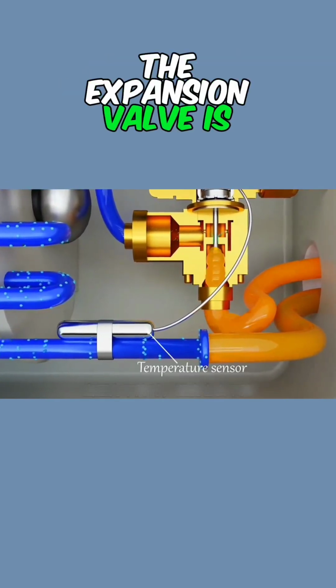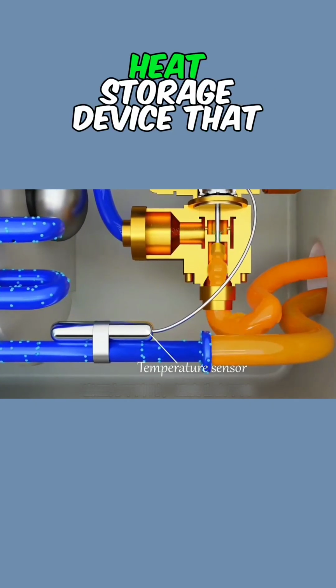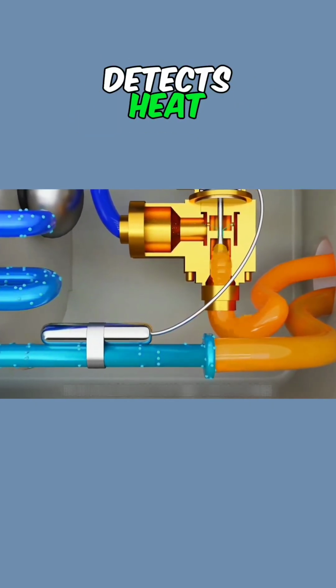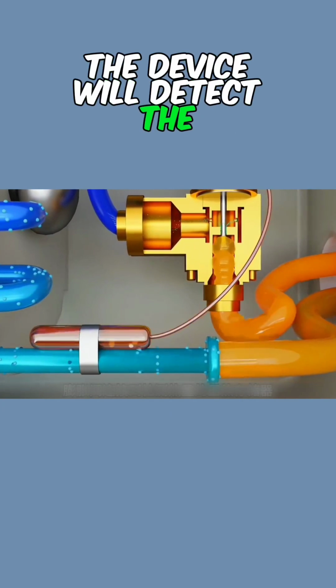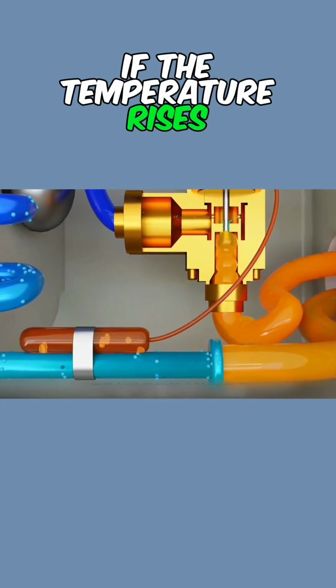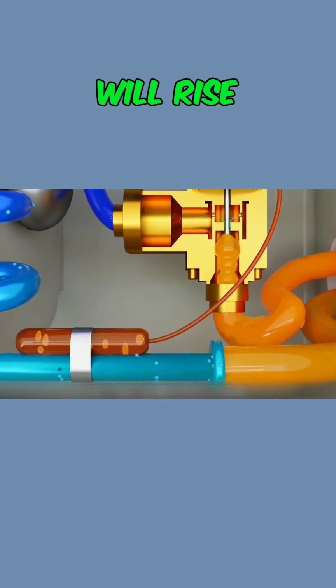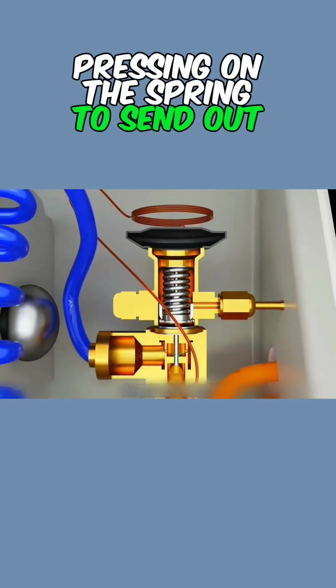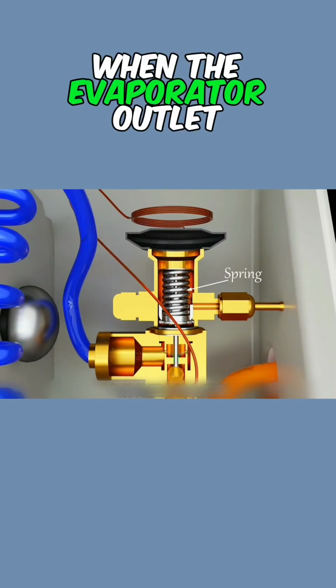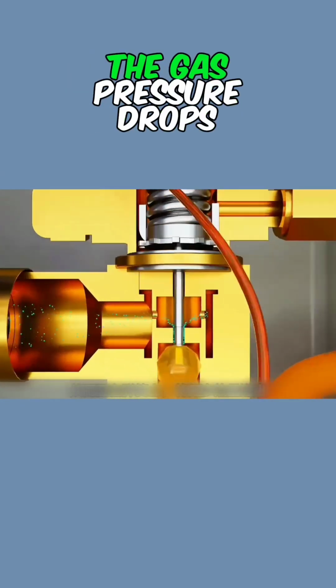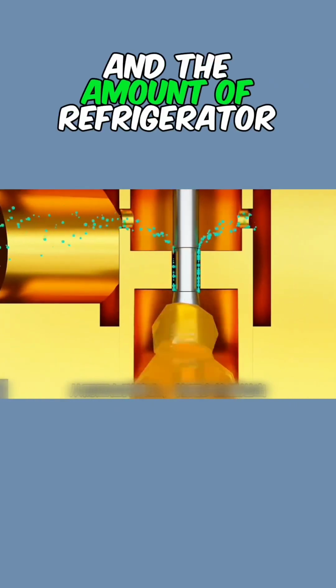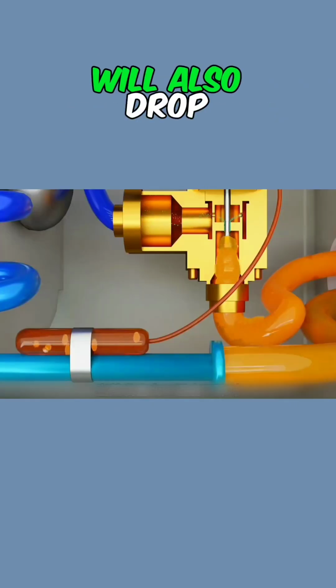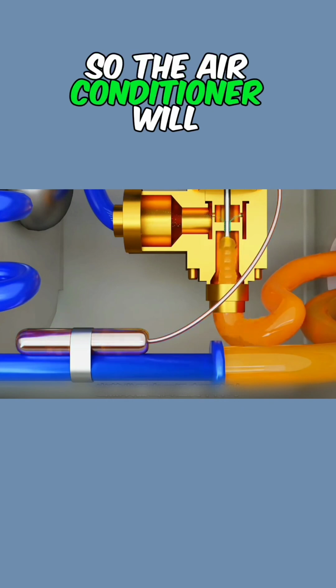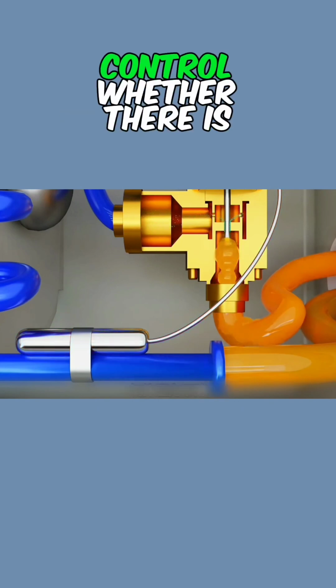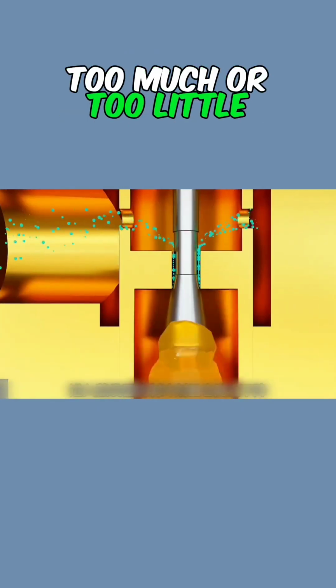The expansion valve is connected to a heat-sensing device that detects heat. The device will detect the temperature. If the temperature rises, the pressure of the gas will rise, pressing on the spring to send out more refrigerant. When the evaporator outlet temperature drops, the gas pressure drops, and the amount of refrigerant entering the evaporator will also drop. It can intelligently control whether there is too much or too little refrigerant.